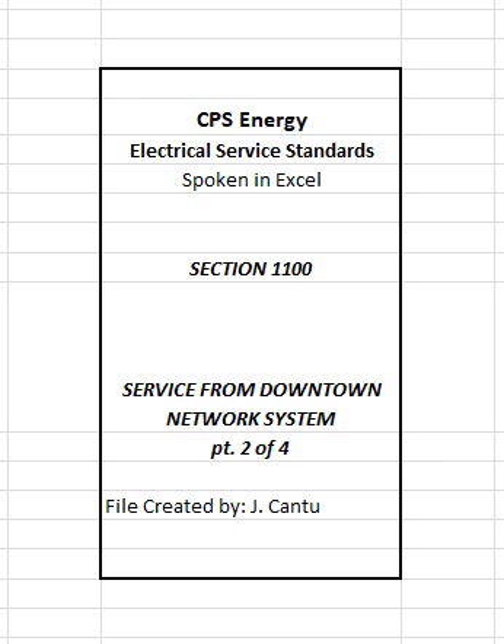4. Where buildings are designed with overhangs or similar type of roof coverings that extend over CPS Energy's transformer vault or room and are determined by CPS Energy to interfere with the installation or removal of CPS Energy equipment, such overhangs and roofs shall be provided with removable hatches or roof covers as approved by CPS Energy. Note: in addition to these basic design requirements, the customer-built transformer vault or room shall meet the specific design requirements listed in E through K below.